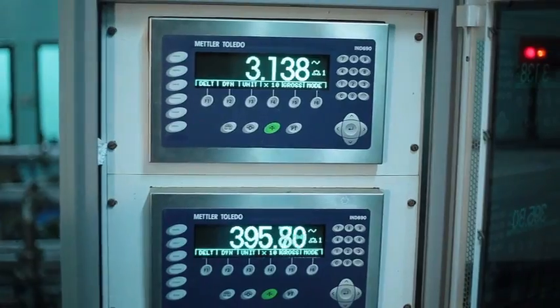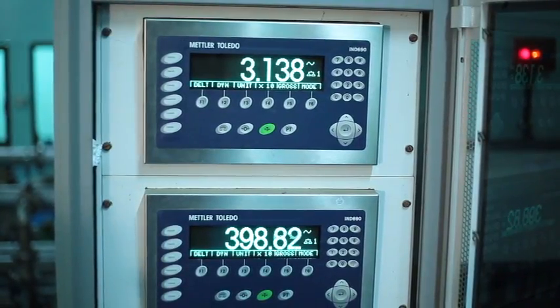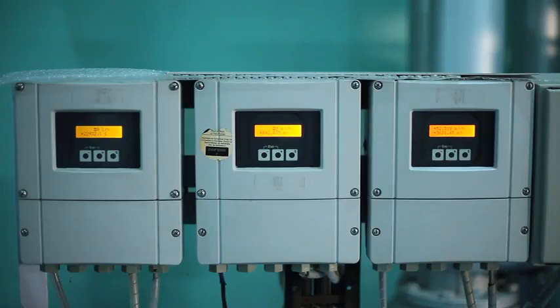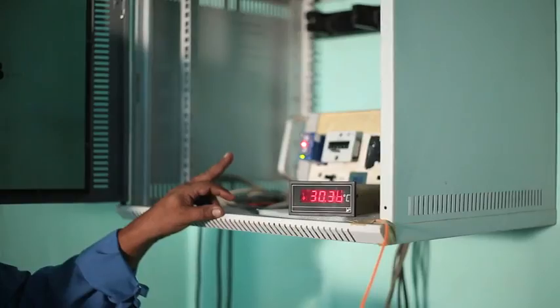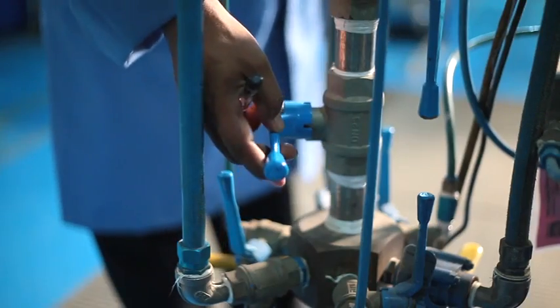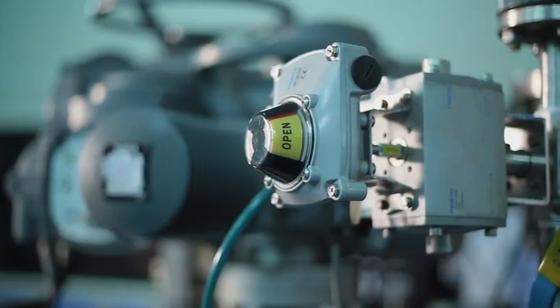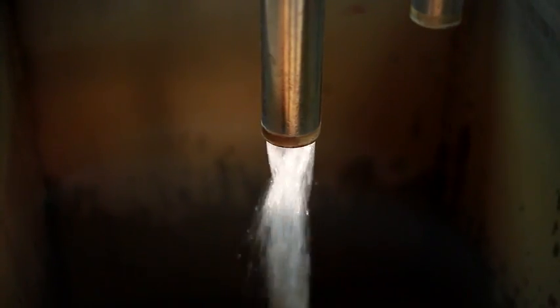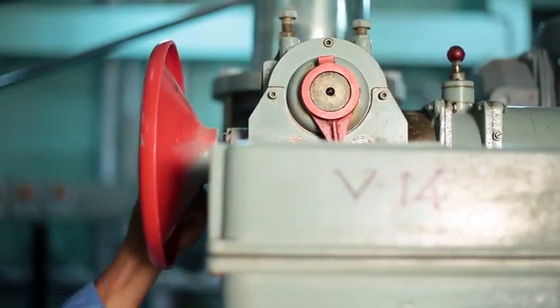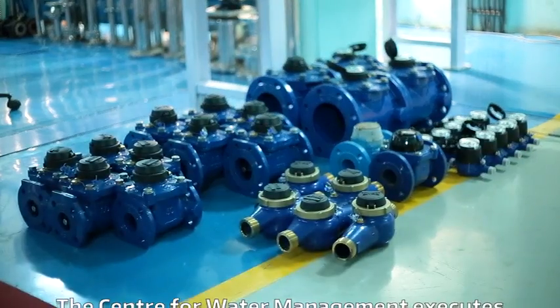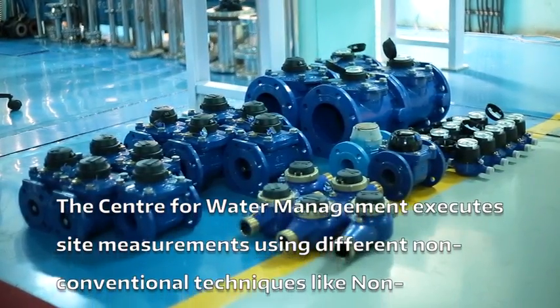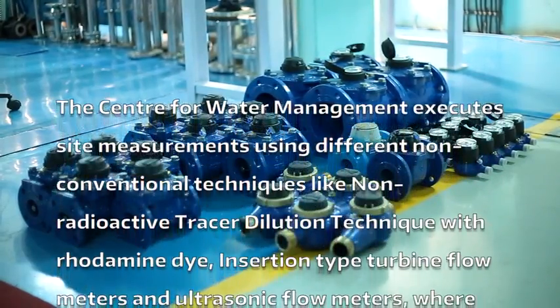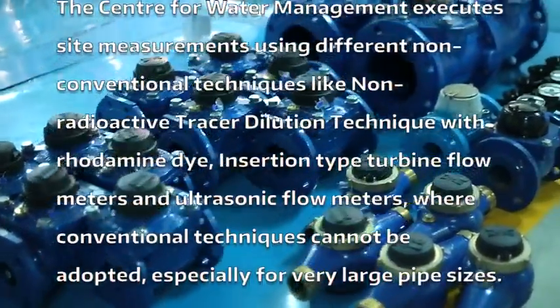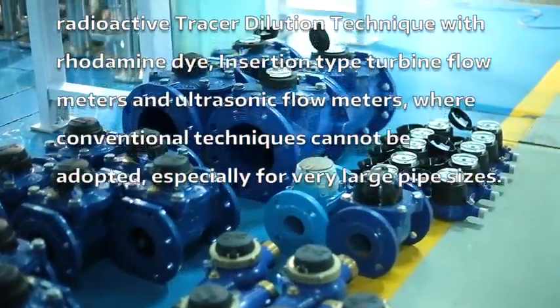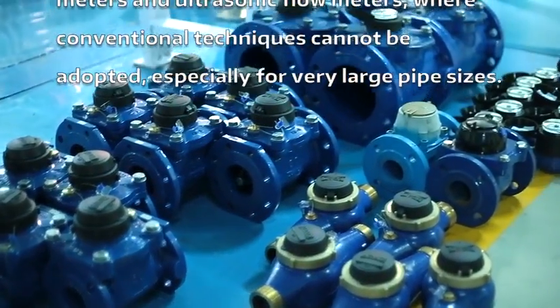It offers accurate measurement of flow in terms of volume, which is determined by the gravimetric system in addition to endurance testing. Thousands of water meters of various sizes are tested here every year. FCRI has played a very vital role in improving the water meter quality in India through its various activities. The center does site measurements using different non-conventional techniques like non-radioactive tracer dilution technique with Rhodamine dye, insertion type turbine flow meters and ultrasonic flow meters where conventional techniques cannot be adopted, especially for very large pipe sizes.